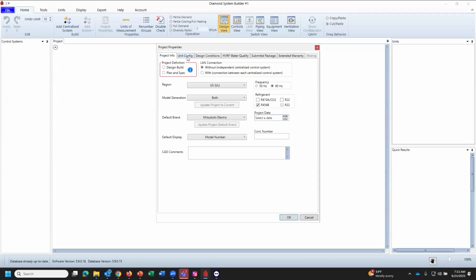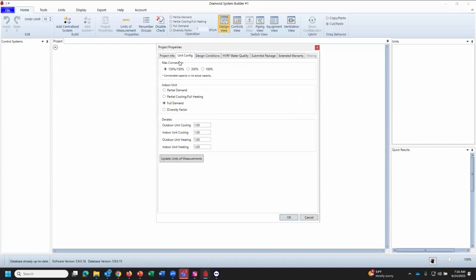So as we go in here, we do have the ability to change the connectable capacity. This is not the actual capacity. In almost all cases, what we're going to see is people use this 130 to 150 maximum capacity, or maximum connected capacity. Some circumstances, guys are using the 200%. If you want the most accurate sizing, then you want to go to 100%. That is going to limit the amount of indoor units that you can attach to an outdoor unit to only 100% of the capacity.